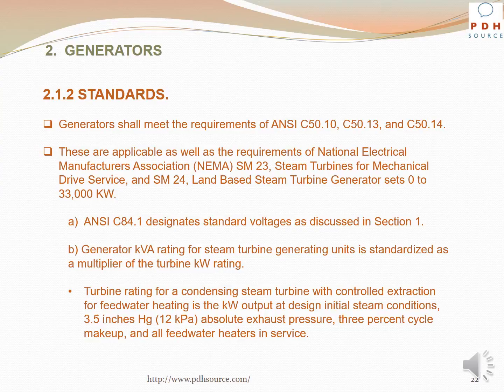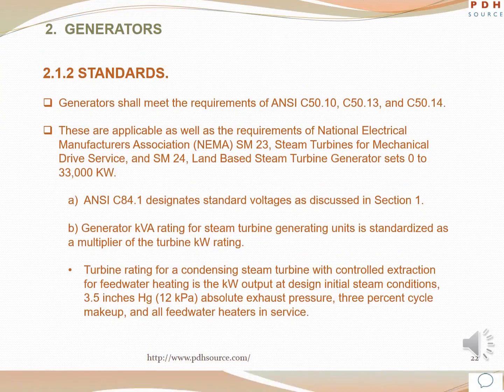Generator kVA rating for steam turbine generating units is standardized as a multiplier of the turbine kilowatt rating. Turbine rating for a condensing steam turbine with controlled extraction for feed water heating is the kilowatt output at design initial steam conditions, 3.5 inches of mercury absolute exhaust pressure, 3% cycle makeup, and all feed water heaters in service.